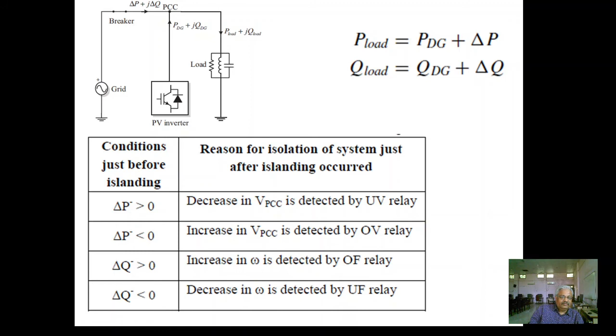Next, delta Q greater than 0 means reactive power was fed to the grid. What will happen when the circuit breaker opens? Previously it was feeding reactive power. Now there is no reactive power feeding. Therefore, the frequency will increase. That can be detected by the over frequency relay. And if delta Q is less than 0, when the circuit breaker opens, there will be a decrease in frequency, detected by the under frequency relay. So by under voltage, over voltage, over frequency and under frequency relays, we can detect the islanding situation.